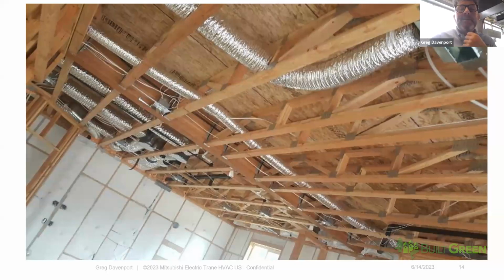This is what the open web trusses look like with ducts inside conditioned space. These are pretty big homes, but because they're building really good envelopes, I think all of their homes are 2.5 or 3 ton systems. So it's a pretty small heating and cooling system because they have low heating and cooling loads with a great envelope. You can see how easy the ducts inside conditioned space is—that ductwork system in the ceiling downstairs has the supplies for downstairs, and in the floors upstairs they have the supplies for upstairs.